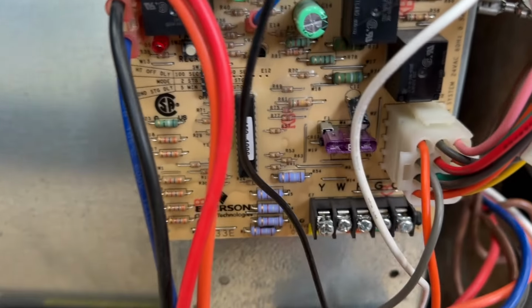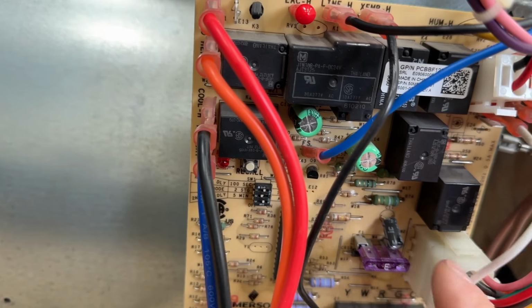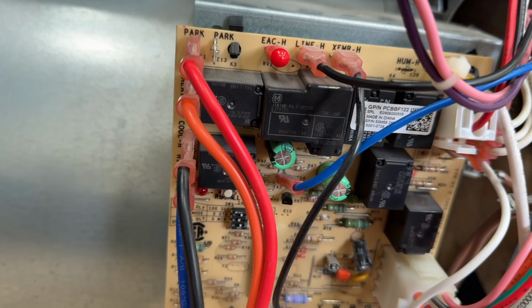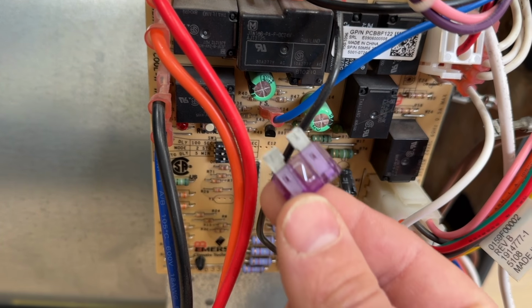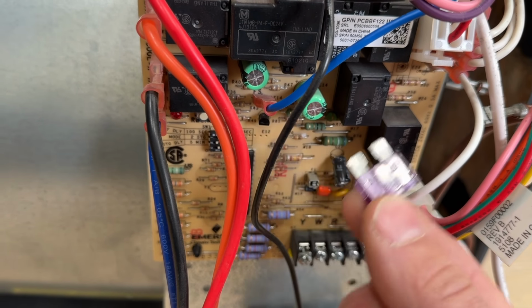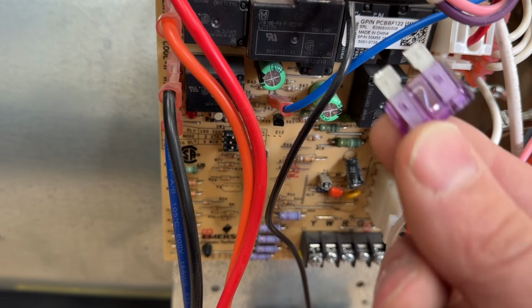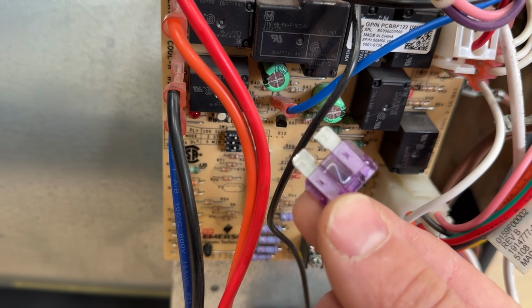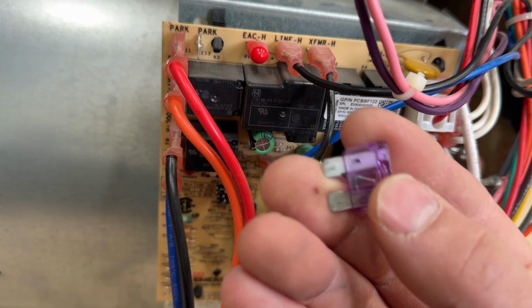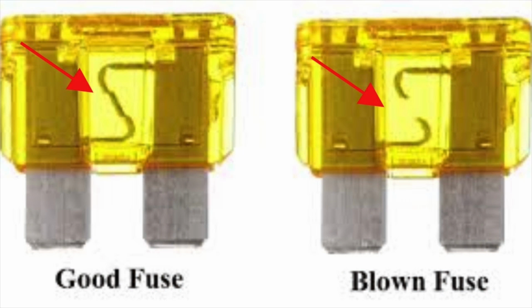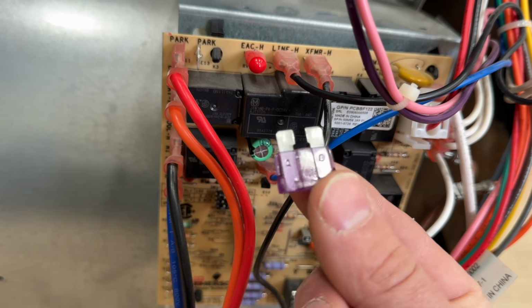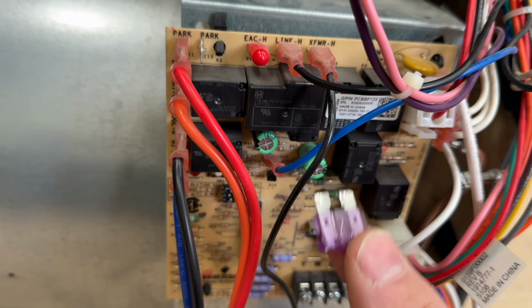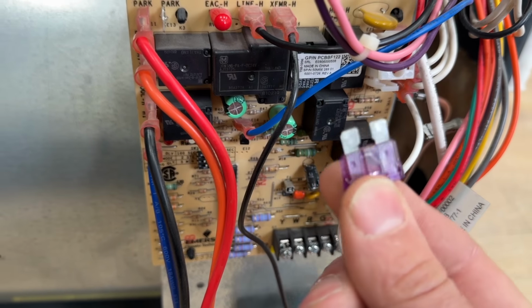Now, while we're looking at the board on this older furnace, you'll notice that there is a 3 amp fuse. So if your furnace is not doing anything, this is something that I would absolutely check. I'm just throwing this in with the blower motor for number 3. So if this fuse is blown, you'll see some black discoloration on the plastic. You'll see this little Z in the middle, that little metal piece will be broken, and there will not be a connection there. That's how you know that this fuse is blown. Sometimes it is as easy as replacing a fuse, and it's something that customers can totally do themselves and save a ton of money.